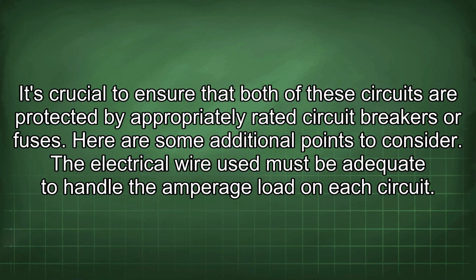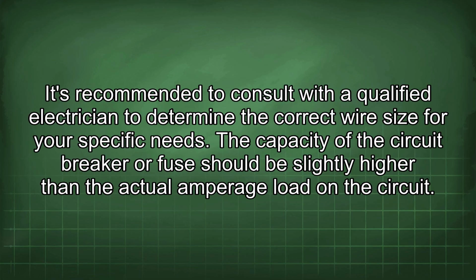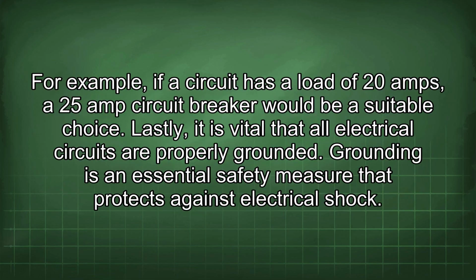Here are some additional points to consider. The electrical wire used must be adequate to handle the amperage load on each circuit. It's recommended to consult with a qualified electrician to determine the correct wire size for your specific needs. The capacity of the circuit breaker or fuse should be slightly higher than the actual amperage load on the circuit. For example, if a circuit has a load of 20 amps, a 25 amp circuit breaker would be a suitable choice. Lastly, it is vital that all electrical circuits are properly grounded. Grounding is an essential safety measure that protects against electrical shock.